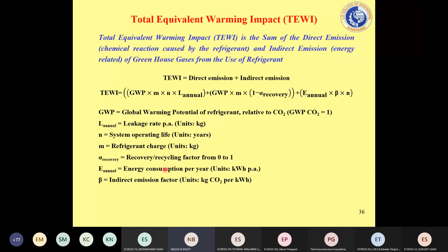So what is TEWI? It's a sum of direct and indirect emission. Now I'm not going to mention each and every term, but you know that the direct emission depends upon the GWP, refrigerant charge, system operating life, and the annual leakage, plus your recovery factor, and indirect emission depends upon your power consumption. For the same case of a 175 watt cooling capacity compressor, if we compare the TEWI for R134A and R1234YF, the GWP of R134A is 1300 CO2 equivalent in a 100 year time frame, while for YF it is just 1. Refrigerant charge is 167 grams for the R134A refrigerator, and it would be 170 for the YF refrigerator.